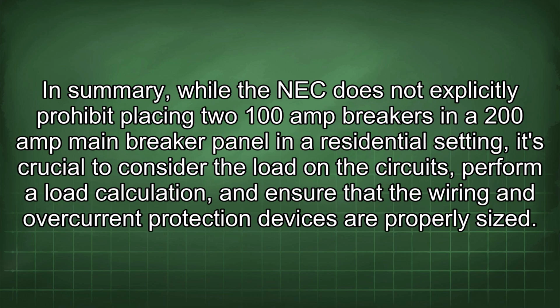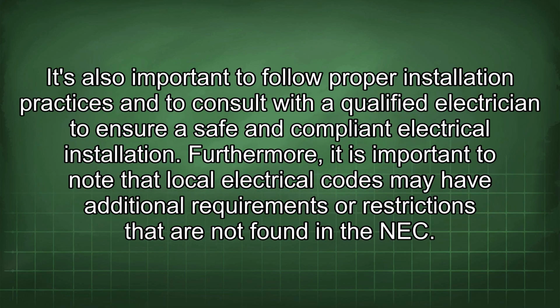In summary, while the NEC does not explicitly prohibit placing two 100 amp breakers in a 200 amp main breaker panel in a residential setting, it's crucial to consider the load on the circuits, perform a load calculation, and ensure that the wiring and overcurrent protection devices are properly sized. It's also important to follow proper installation practices and to consult with a qualified electrician to ensure a safe and compliant electrical installation.